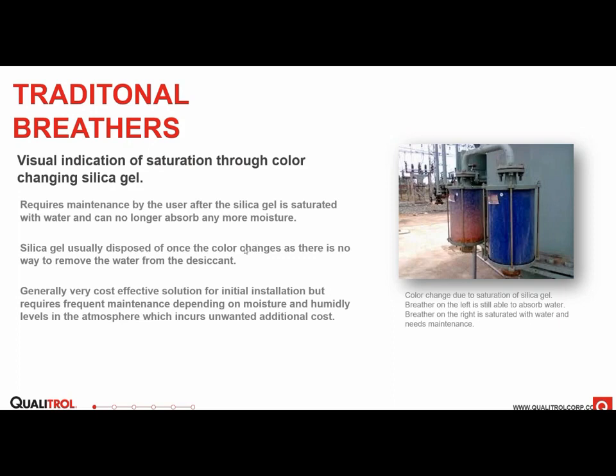Is it actually doing its job still? And at any time, it can allow moisture to be sucked into the transformer if the silica becomes fully saturated, either quicker than expected and the crew doesn't get to site in time to do the replacement, or the visual indication, the color changing, maybe stops working. There's a lot of variables there.